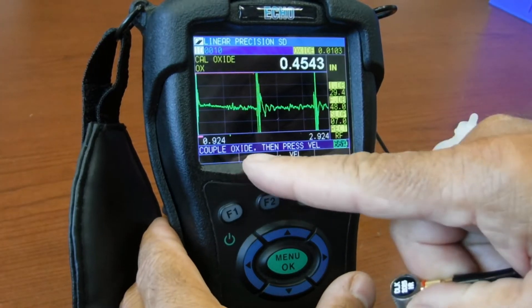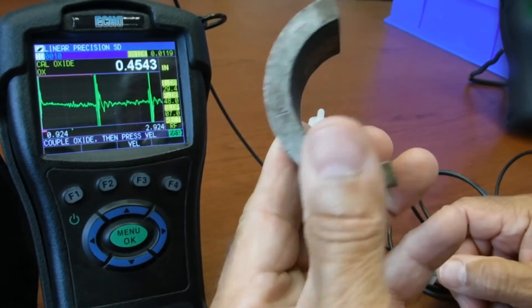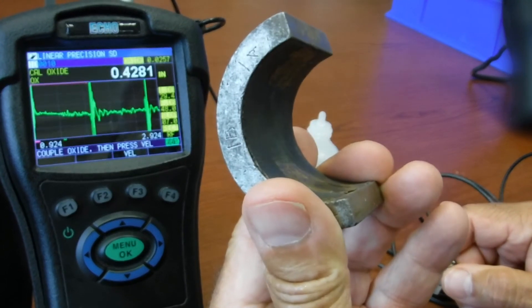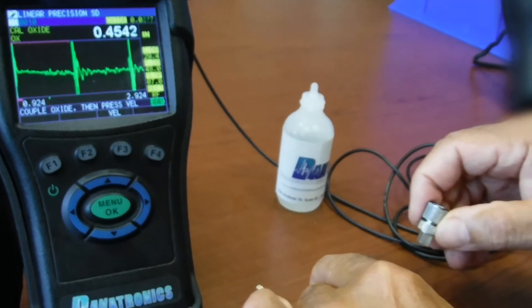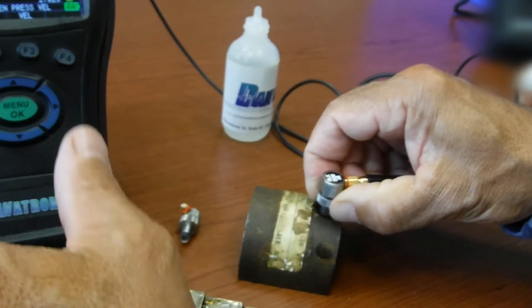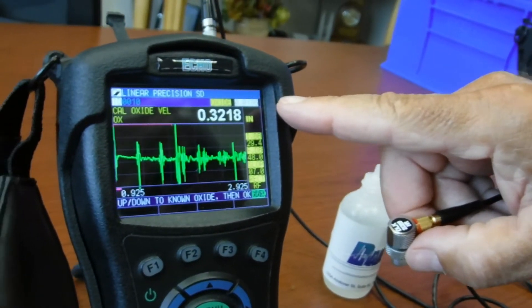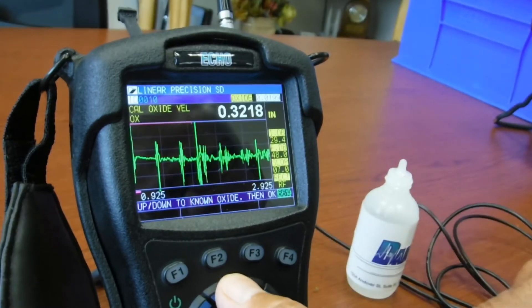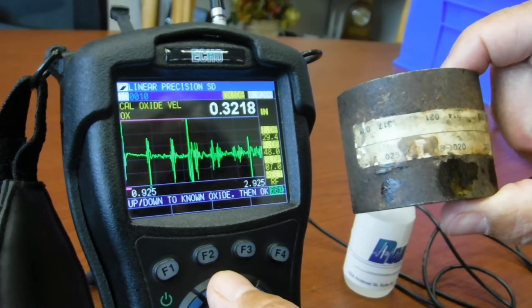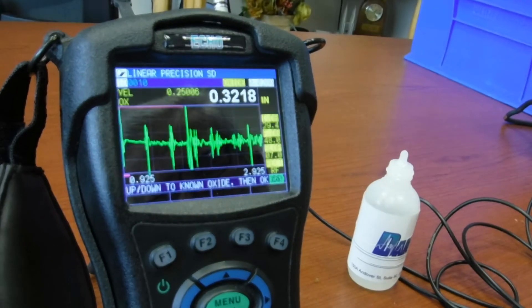Now the prompt says couple oxide and then press VEL. Here we have a sample of some oxide scale, roughly twenty thousandths of an inch on the inside of a tube that's roughly three hundred and twenty thousandths. I couple and I press the F3 VEL key. The number in the top right of 0186 will be scrolled up to 020 as indicated on the test sample. I press menu OK and the oxide velocity is calculated.